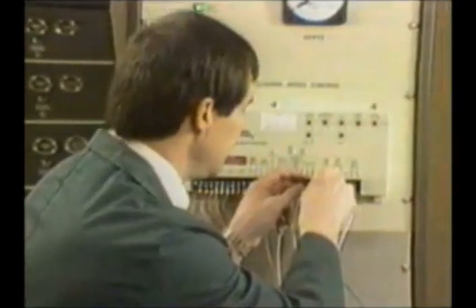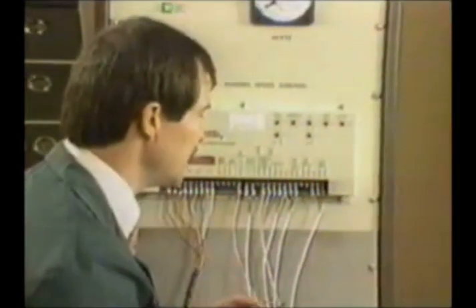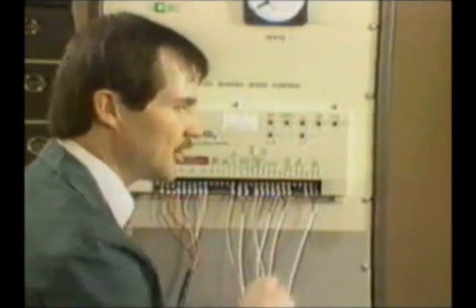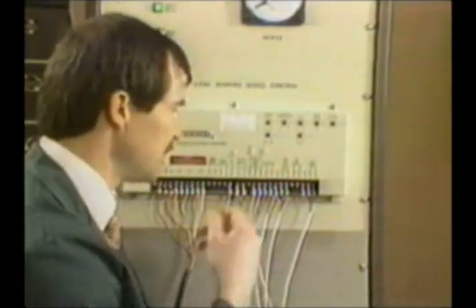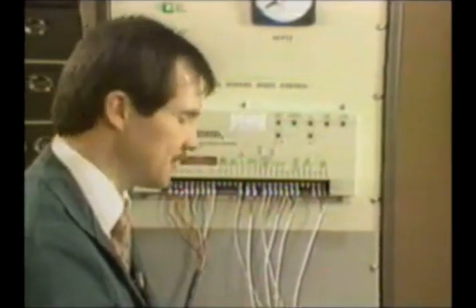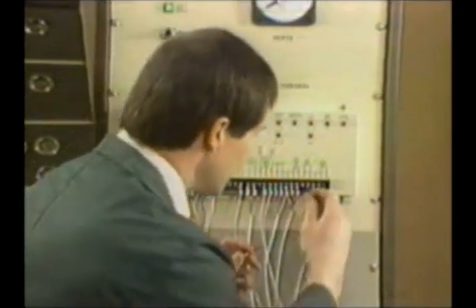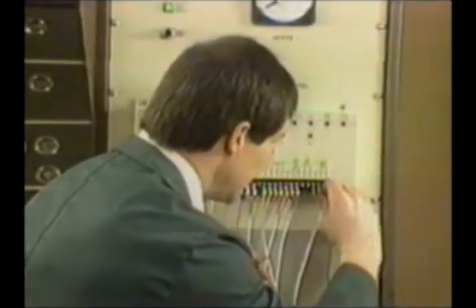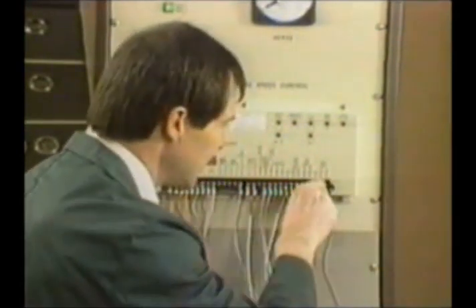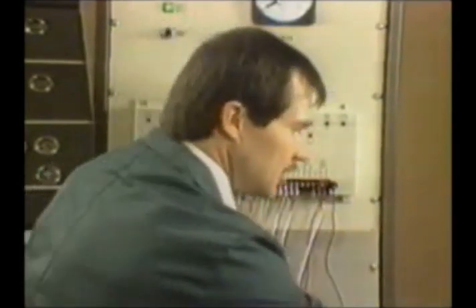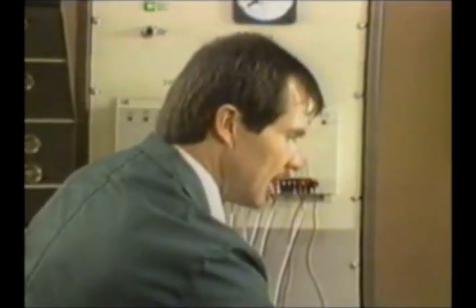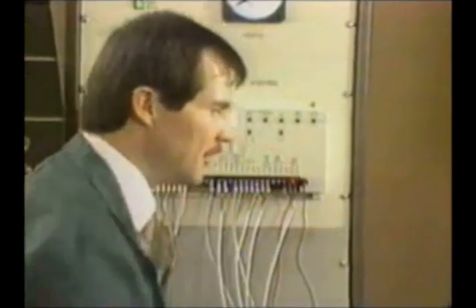Now the last check you need to do before you start up is I want to make sure my speed signal input is correct. I want to make sure I'm getting enough voltage there so I can start. So I'm going to hook up to terminals 29 and 28. I need to go into the AC mode, and I'm going to go down to my 20 volt scale.